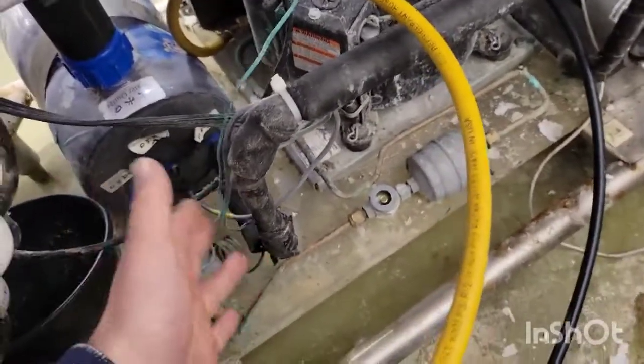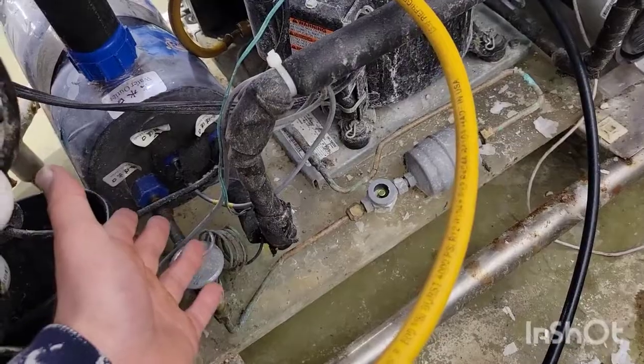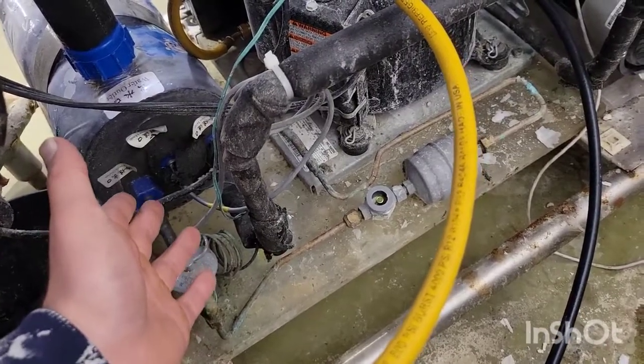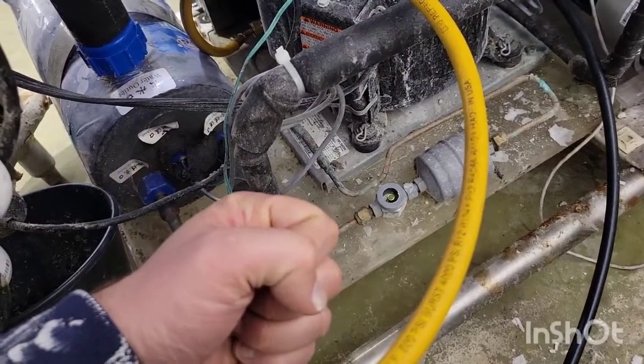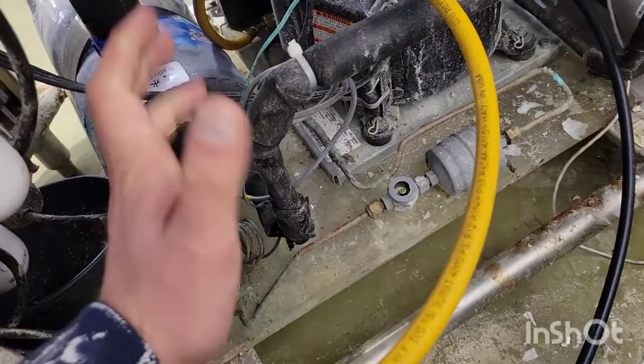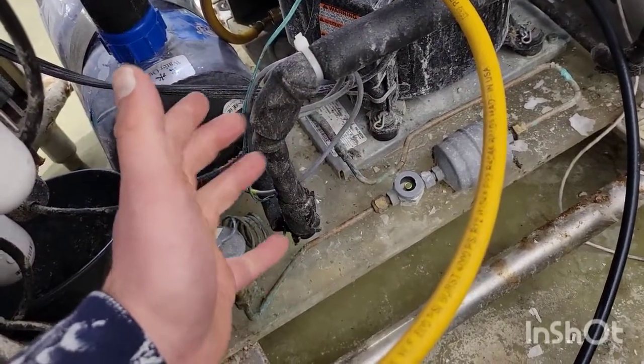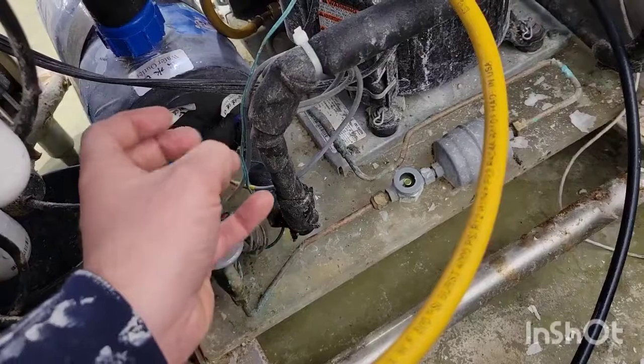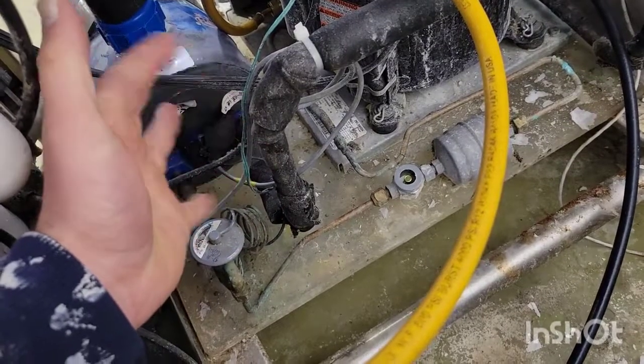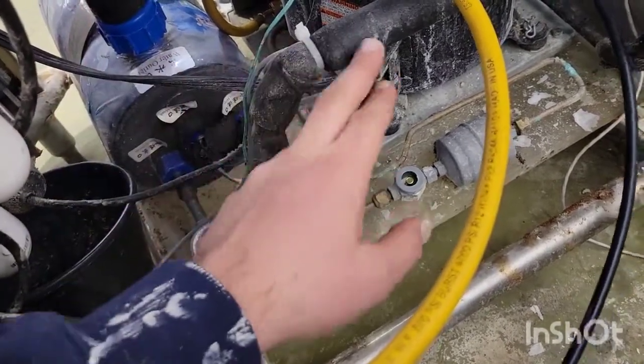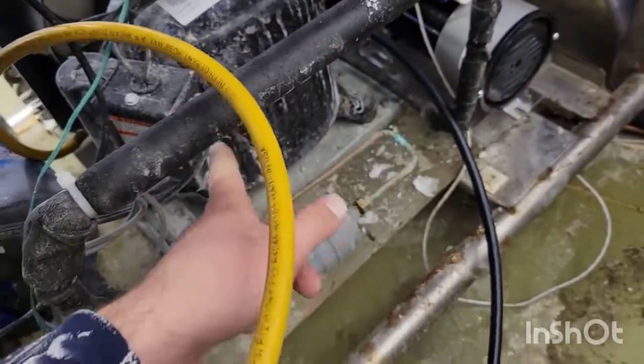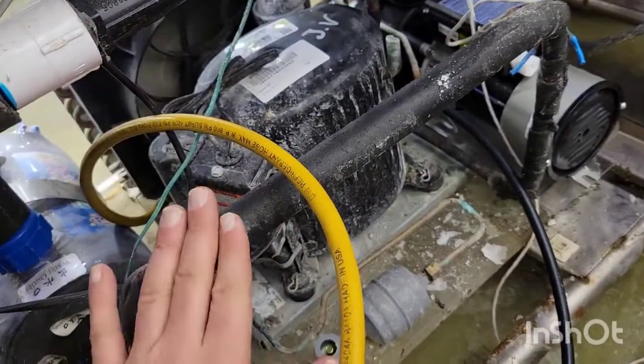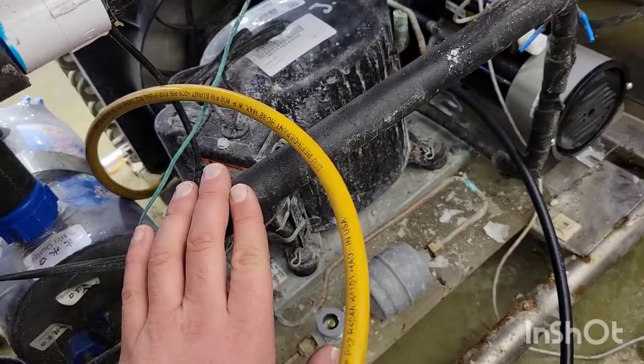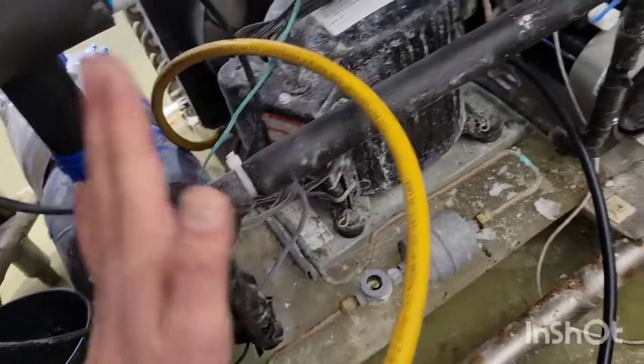This water right here is 50 degrees. That evaporator coil is, let's say, 32, 38 degrees right now. And what happens is the warm 50 degree water sheds its heat to the cooler 38 degree coil. That refrigerant absorbs the heat energy in that coil, comes back through the suction into the compressor and blows out the discharge over there. So this is just a glorified chiller.